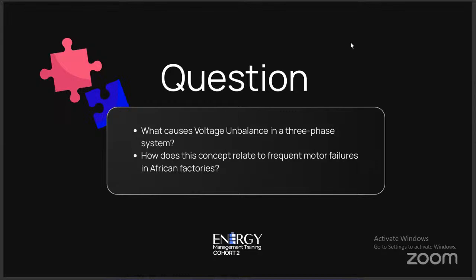Let's have Mr. Francis Adekunle. Unmute yourself. Okay, so for the causes of voltage unbalance in a three-phase system, I think one of the major problems is usually the load distribution. If the loads are not distributed evenly, then some phases will be drawing more load than the others, which can cause voltage unbalance in the three-phase system. And also, the phase angle between each of the phases can cause it. They are meant to be separated by 120 degrees from each other. If they're not adequately separated, then it can also cause voltage unbalance.